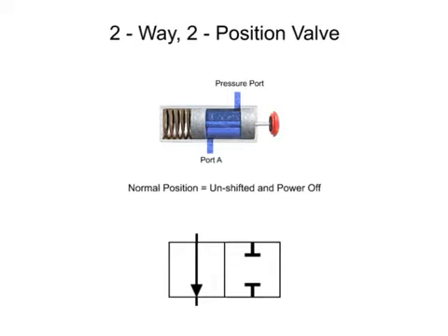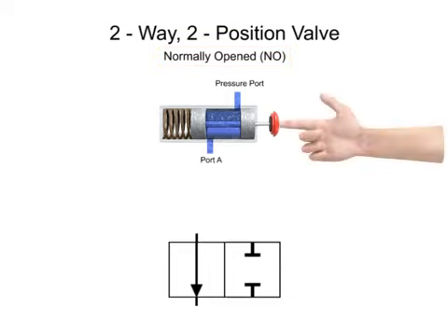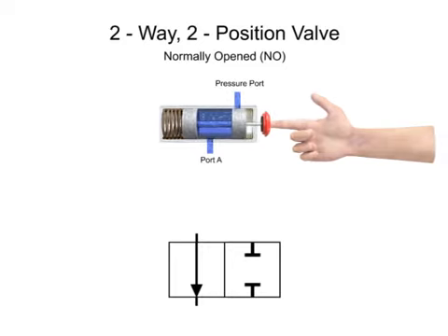The terms normally open and normally closed are used to describe the condition of a valve when it is in the normal position. For this valve, the normal position is position one, which allows unrestricted fluid flow through the open ports. Therefore, this valve is a normally open valve. Additionally, this valve is a spring return valve, meaning that after it is actuated, a spring returns the spool to the normal position.